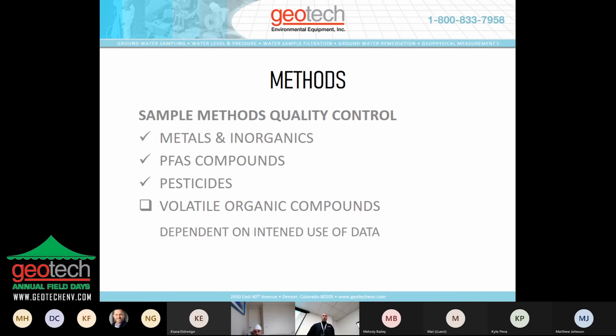It is also used for volatile organic compounds, VOC sampling. However, there is some debate out there and some documentation out there where people are worried about the fact that since it's a vacuum lift pump, it might volatilize the sample. So be careful with which agency you're working with. They may not want the peristaltic pump used for that. However, I can tell you in 20 years of selling and working with these devices and working with our customers, I have not had one come to me and tell me that they had lost a sample. So this is dependent on intended use of data, of course. So keep in mind, you want to make sure that you're in compliance with who you're working with and who you're reporting to.